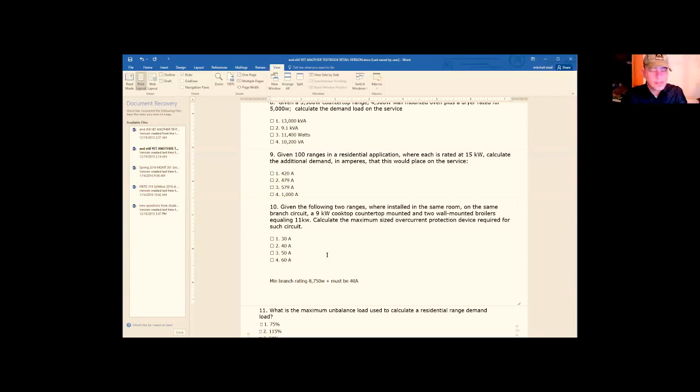And then there's another code rule back in Article 422.11(B). Let's go back and look at it real fast. It's on page 303, I think. On page 303 in the left-hand column under B, household appliances and surface heating elements, which is a range. Those can have a maximum demand of not more than 60 amps, but they can't be protected with any circuit breaker larger than 50 amps.